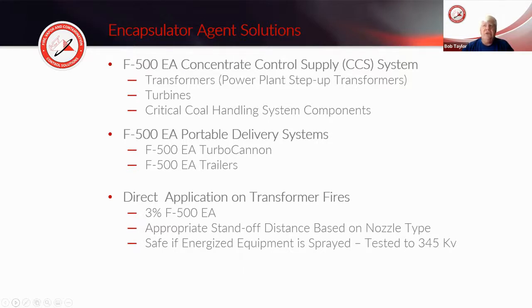So there's a couple things to think about. The encapsulator agent is sometimes applied through an F500 concentrate control supply system, commonly on transformers, turbines, lubricating oil systems, and key hazard-handling areas like conveyors, dust collectors, energy storage systems, and lithium-ion battery systems. Some have used it in a portable mode, with F500 in bulk supply on a trailer or truck, so it can be located where needed and introduced with water at the proper concentration using the proper equipment.